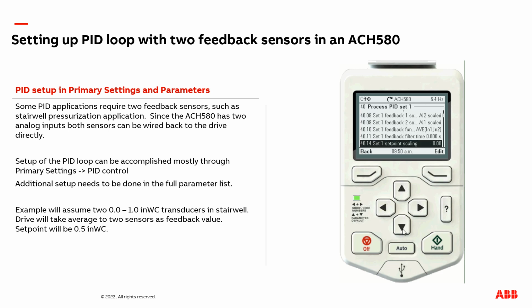Now, the final setting we need to adjust, because we're doing two feedback sensors into the drive, I recommend you adjust parameter 4014 to the maximum value of your transducer range. In our case, it's a value of 1. We have a 0 to 1 inch of water column, so I'm going to adjust parameter 4014, set point scaling, to 1. This is not adjusting the set point that is programmed in the drive. This is adjusting some scaling behind the scenes. I just recommend you adjust it to the maximum value of your transducer range. Now, this completes all the programming in the drive to accept 2 analog input signals or 2 feedback signals for your PID loop.